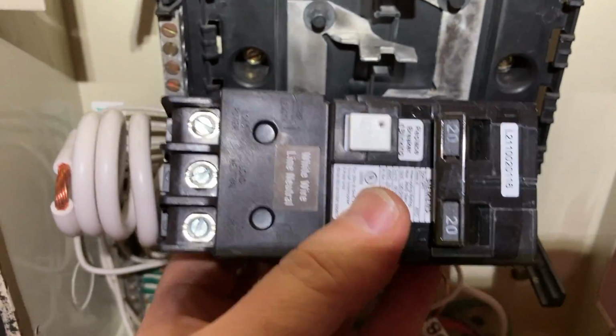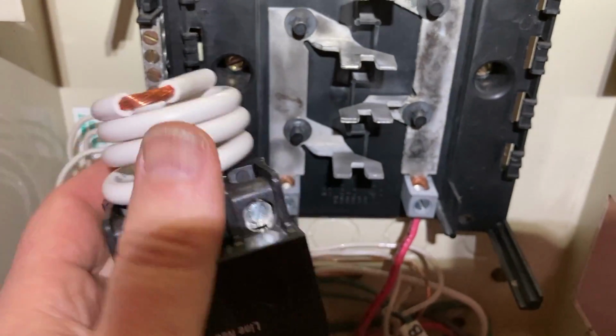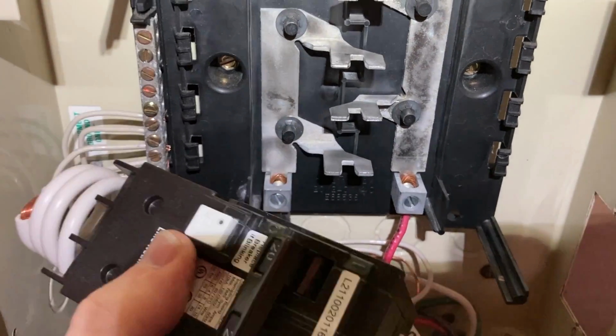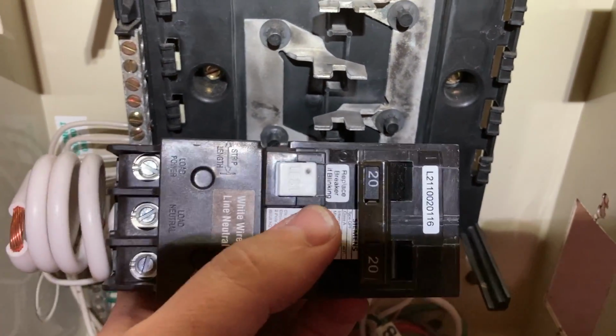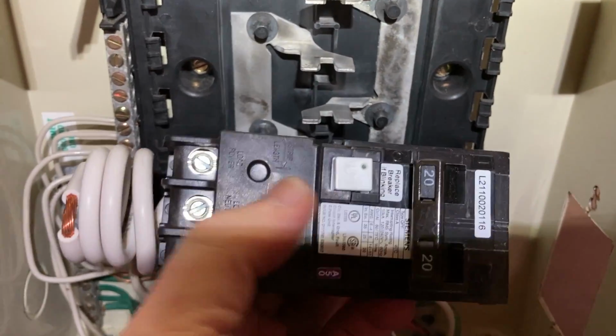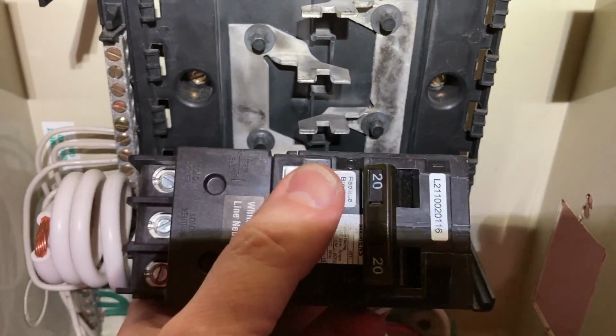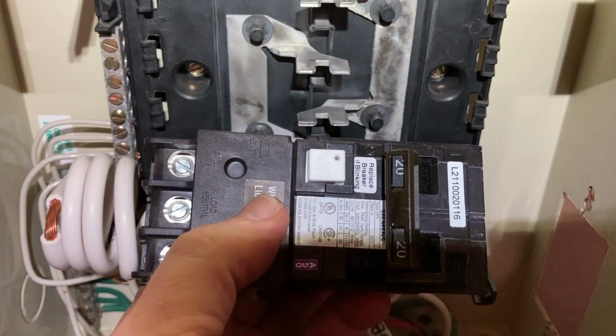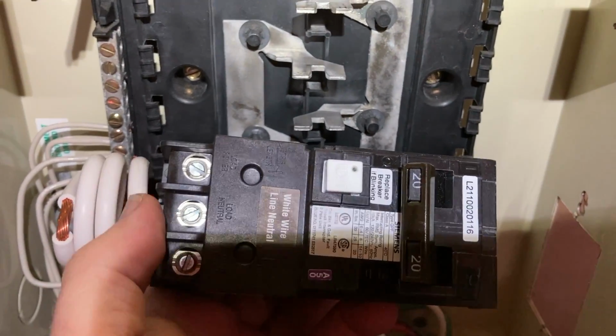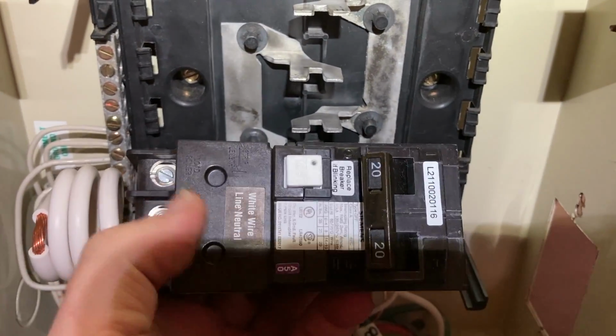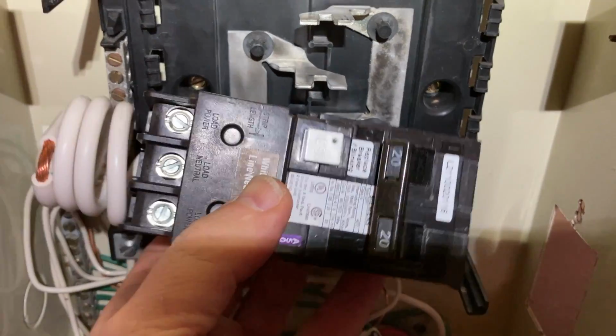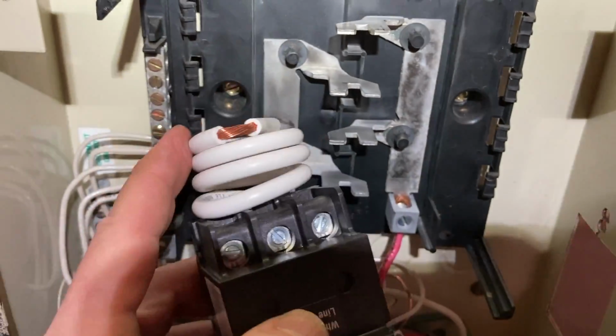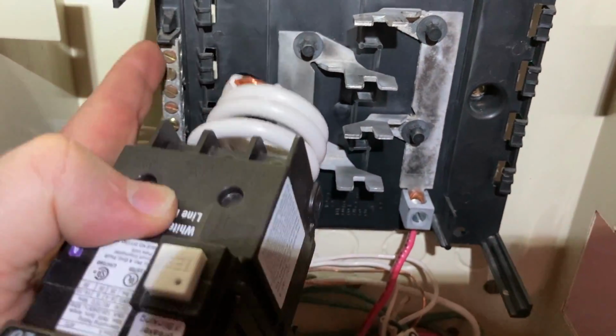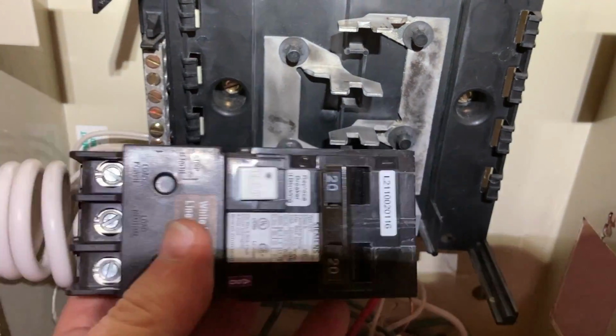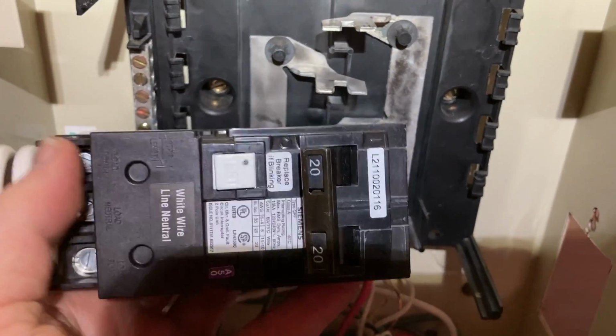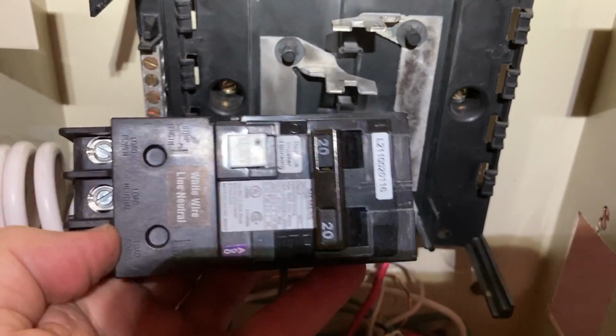And you still need to connect the white wire to the neutral bar because, for one, the test switch works by grounding to the neutral, so you want that to work. And the other is the electronics in here take their power from 110 volts to neutral. They go through a full wave rectifier to the circuit board. So anyway, we will connect this to the neutral bus, which should be fun to get in here, and we will connect the 2 black and red load wires to the pump.